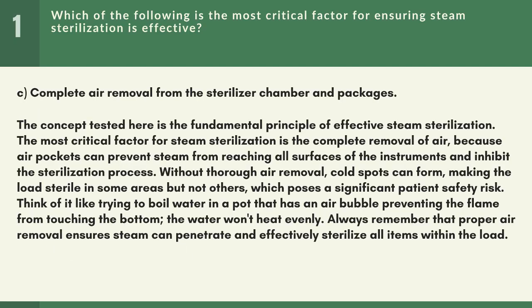Answer: C. Complete air removal from the sterilizer chamber and packages. The concept tested here is the fundamental principle of effective steam sterilization. The most critical factor for steam sterilization is the complete removal of air, because air pockets can prevent steam from reaching all surfaces of the instruments and inhibit the sterilization process.